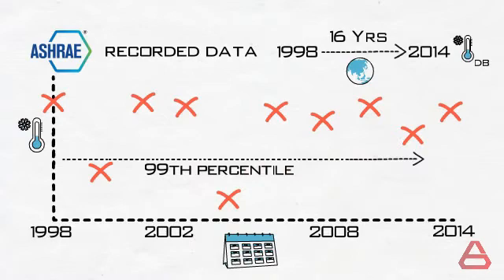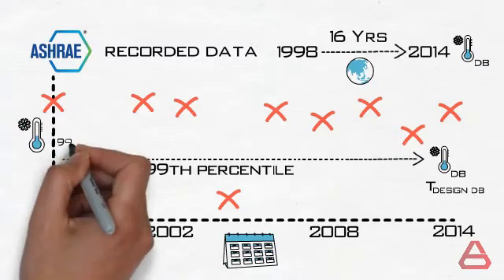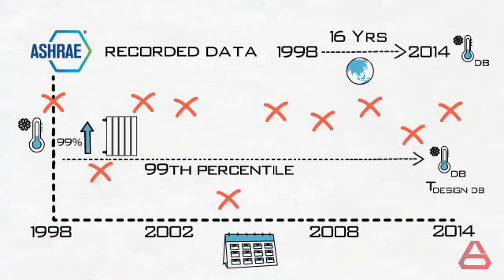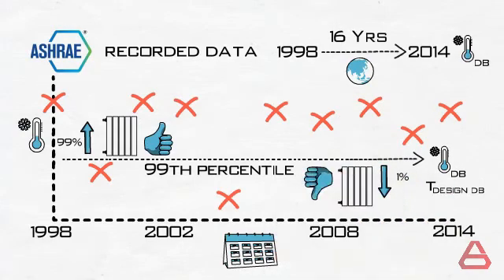The 99th percentile simply means that for this number 99% of the recordings taken are above this temperature. Ergo you or your heating system will be able to counter the load produced from such temperatures. Over the years this has proven to be quite successful. What about the other 1% you might ask? Well yes your heating system will tap out. But as explained before the temperatures that fall below this number are really rare. They have very low frequency. Therefore considering them will do more harm than good if I may.